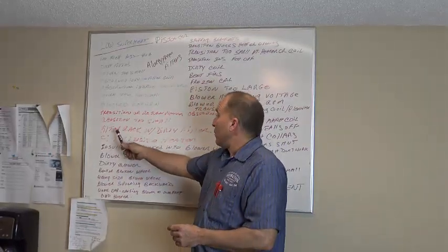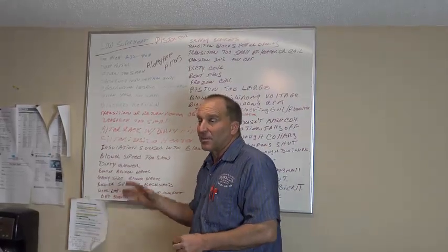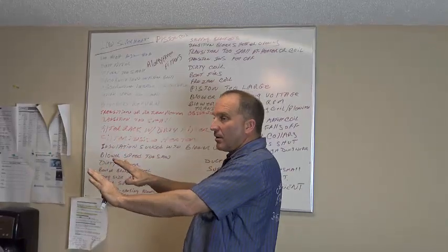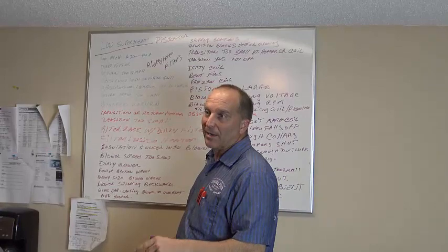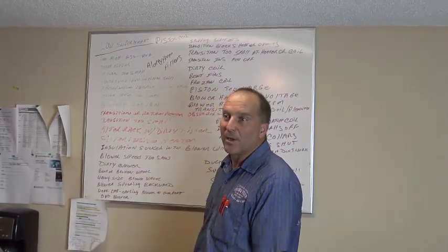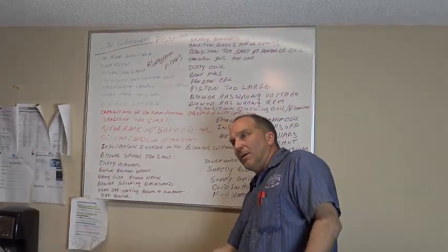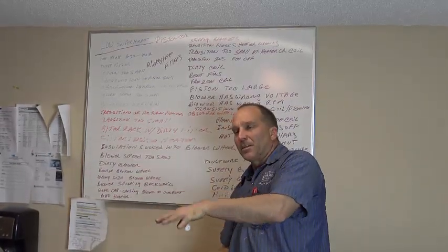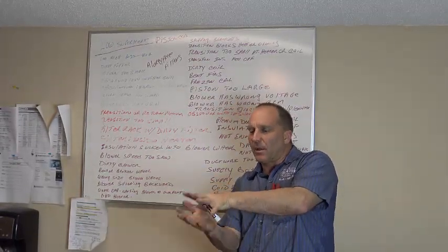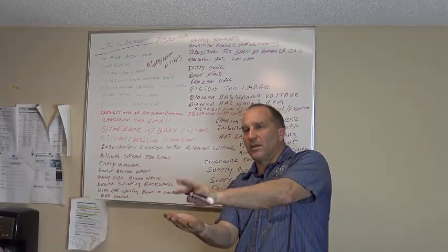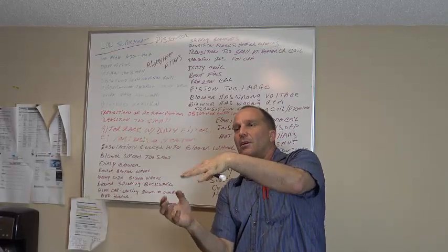Okay? Your filter rack with a dirty filter inside of it, a lot of times that filter rack before the heater, they don't even know that filter's there half the time. So anytime you see a filter rack in a horizontal application, you better go open it, because what you're going to find is a filter that's been blown through and ripped apart because it's so dirty and that blower motor is sucking that airflow through that finally it ended up weathering that paper down and blew holes in it. Your filter being pleated is going to open up and blow that air right on through, and all the dirt and everything's going to get all in your blower motor.